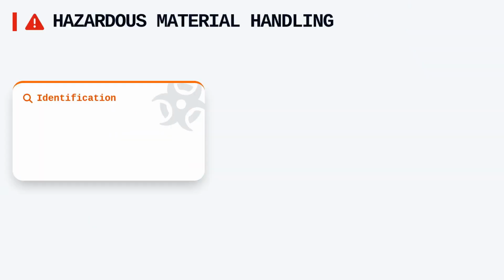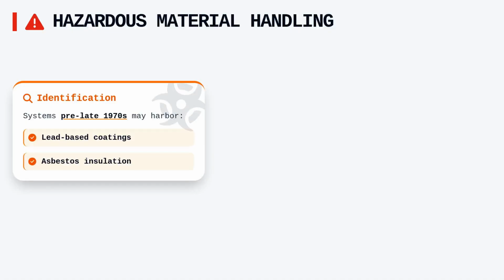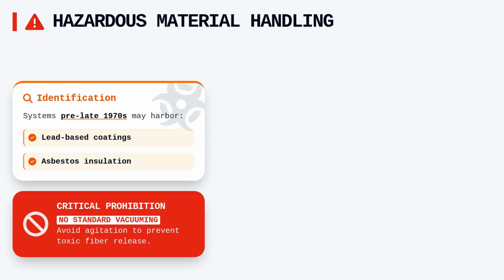Dealing with high-risk materials such as lead-based paint debris or asbestos-containing materials demands strict adherence to both OSHA and EPA mandates. Many older HVAC systems, particularly those installed before the late 1970s, may harbor components treated with lead-based coatings or insulated with asbestos that has begun to degrade. You cannot simply vacuum these materials into a standard bag, as this would violate basic safety protocols and potentially release hazardous fibers into the air you are tasked with cleaning.